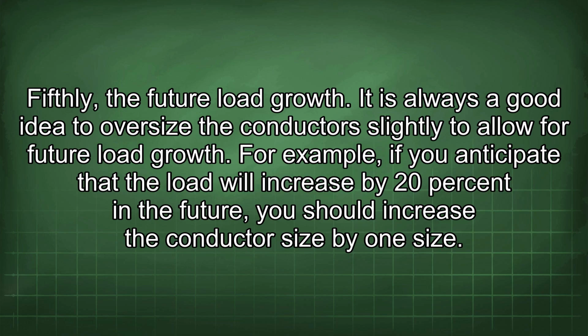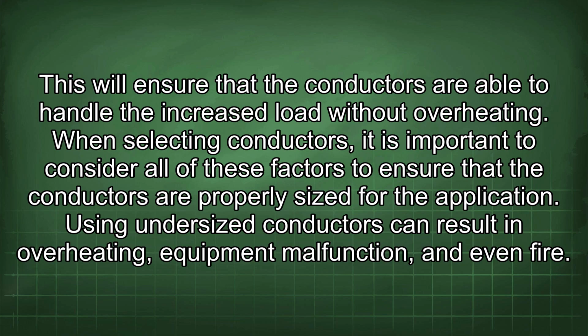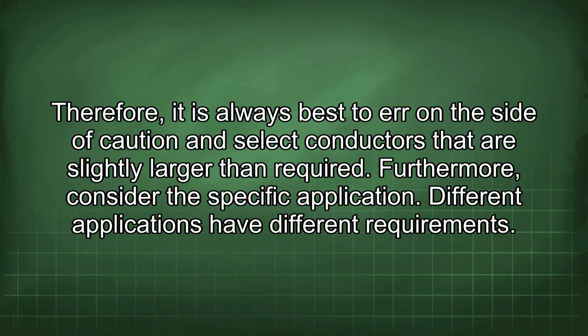Fifthly, the future load growth. It is always a good idea to oversize the conductors slightly to allow for future load growth. For example, if you anticipate that the load will increase by 20% in the future, you should increase the conductor size by one size. This will ensure that the conductors are able to handle the increased load without overheating. When selecting conductors, it is important to consider all of these factors to ensure that the conductors are properly sized for the application. Using undersized conductors can result in overheating, equipment malfunction, and even fire.